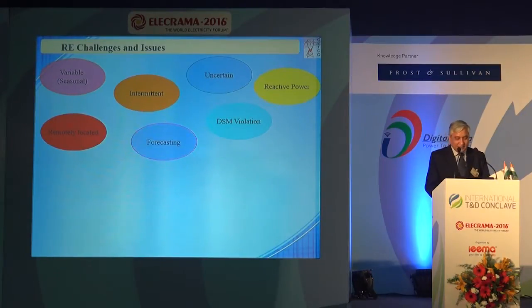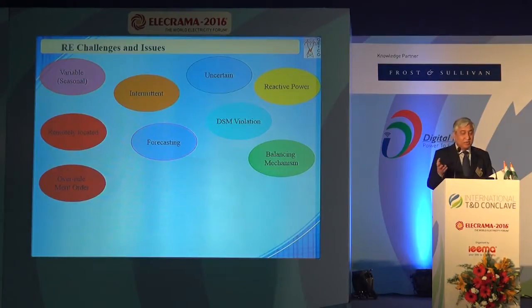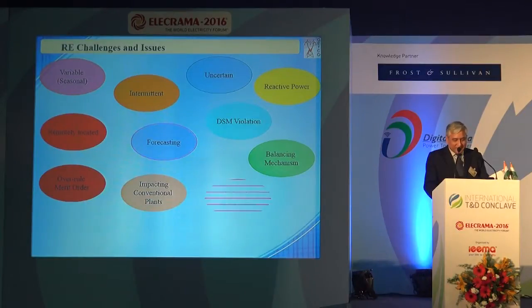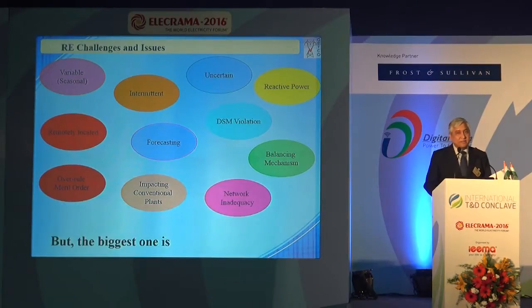Forecasting, I think, is the answer to many of the issues I've been discussing. Then there's the mandatory must-run order: I'll show you cases where 1 rupee 55 paisa power is stepped down and wind power at 4 rupees 13 paisa is allowed onto the grid instead, which we are required to permit. This also impacts conventional plants, which have to run at technical minimum. Then there's network adequacy — many times the network isn't adequate; for example, when there's a peak of 2500 in my own network, in those areas it won't be able to serve that demand.